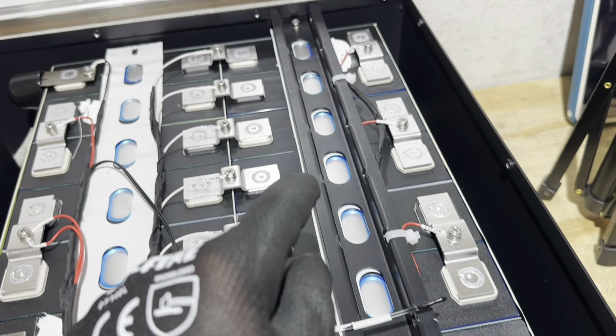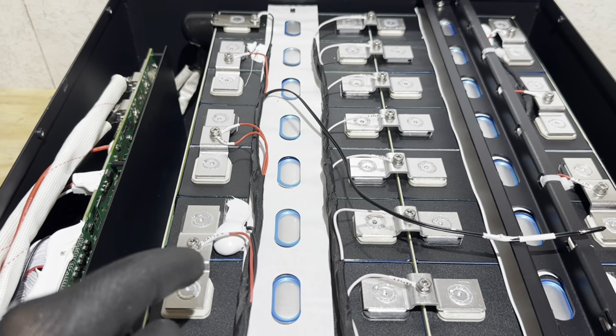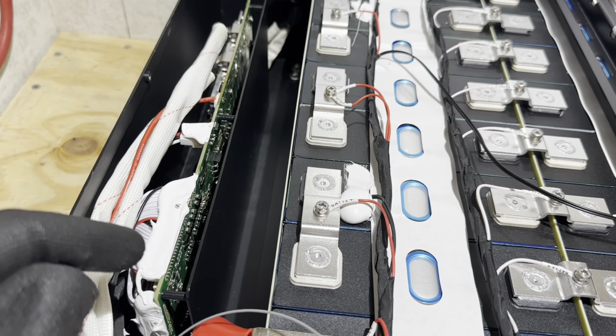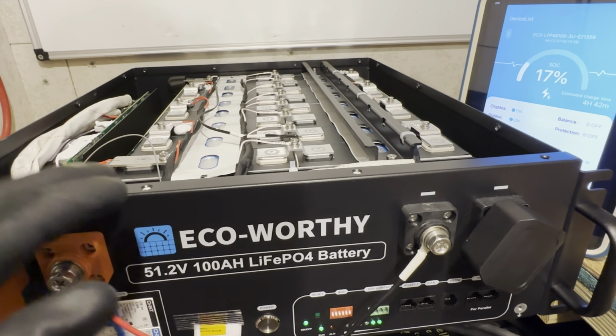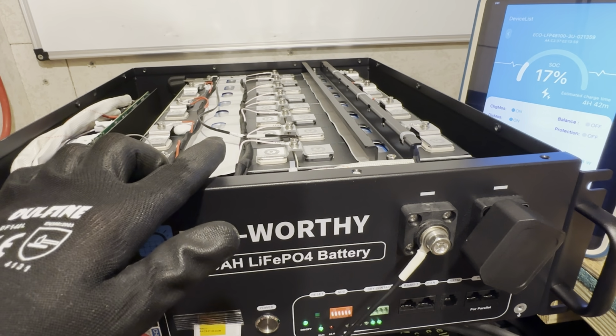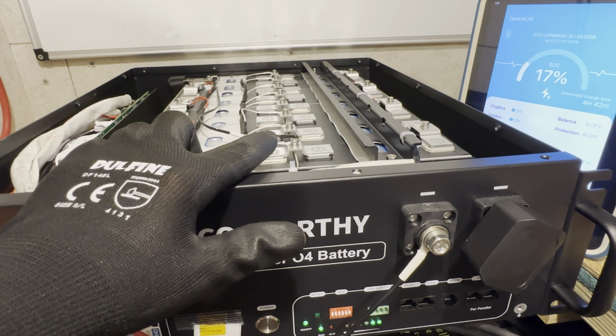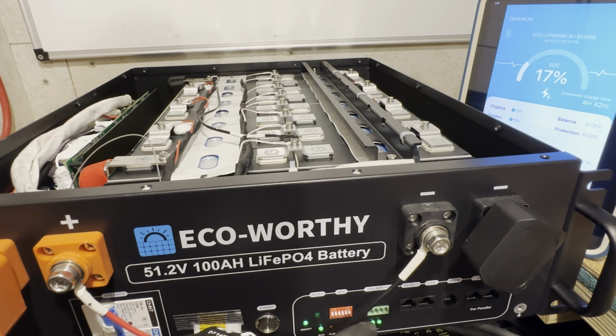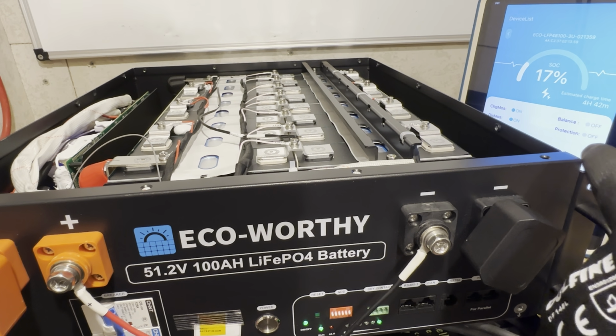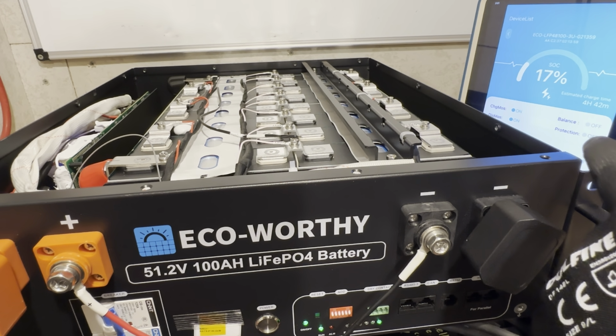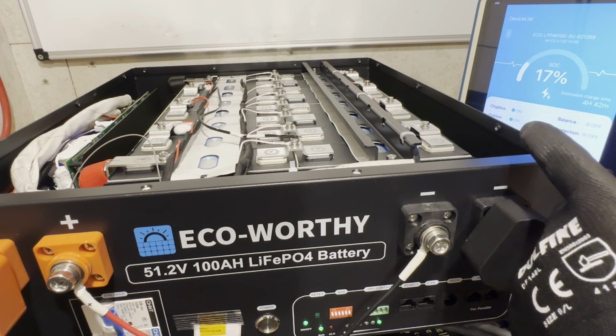We have 1, 2, 3, 4 on the cells, and then there's a chip on board on the BMS as well. I've got the battery charging now. I'm going to check for high and low temp charge protection off that sensor right there in just a moment. You can see on the LEDs on the front that we're flashing, which means we're charging. I set the iPad up here where you can see the protection switches for charge and discharge.